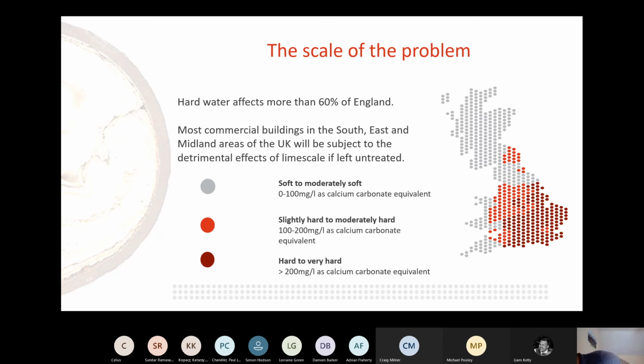Sorry, Craig, you were going to say something? Yeah, we've got a lot of customers that start the specification at 100 ppm and above of calcium carbonate, CaCO3, so they start at that level. Even in my area it's about 137 ppm, and on a domestic system I get lime scale. So on a commercial system where you're using a lot more water, you're going to get lime scale coming out of solution.